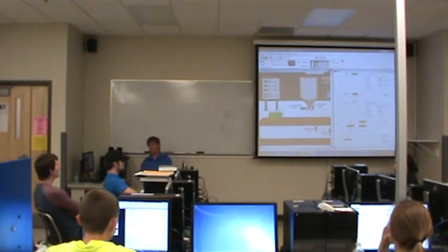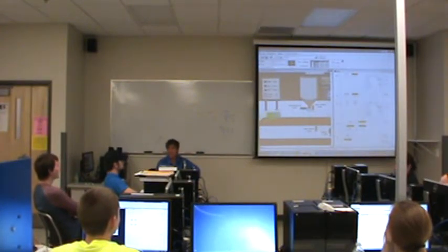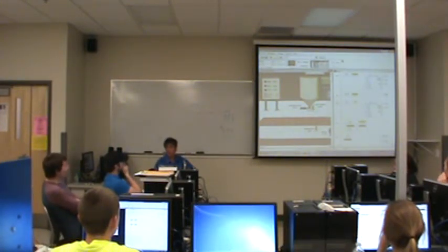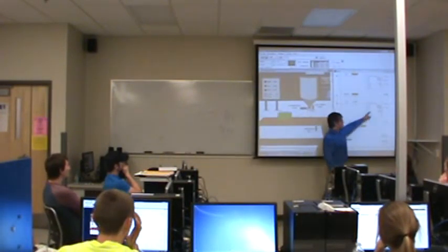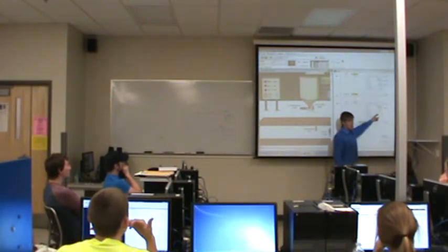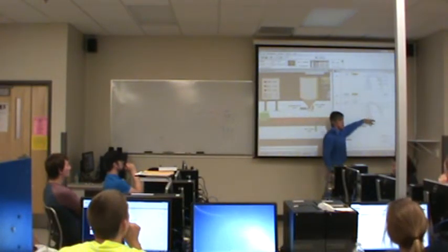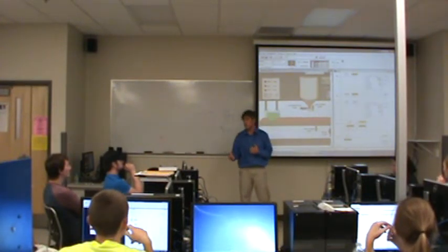Now, one more thing, one very last thing. You hit stop and it doesn't stop. Well, that might be a problem, right? Because when the user hits the stop button, they expect everything to shut off. What happened? Well, I stopped it there on purpose because the only thing controlling the motor output is this sequence output instruction. And when I hit stop, that killed this seal-in, which killed the instruction. It doesn't have the opportunity to turn the motor off, and it probably wouldn't anyway because it's going through the next step of the list.